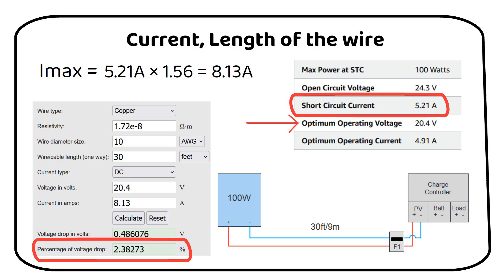For efficiency and cost savings, position the charge controller close to the battery. This minimizes energy loss by reducing the need for thicker, more expensive wiring due to the lower voltage and higher current in these cables.